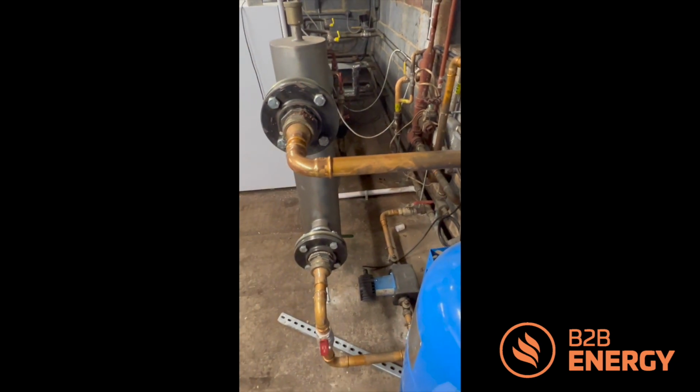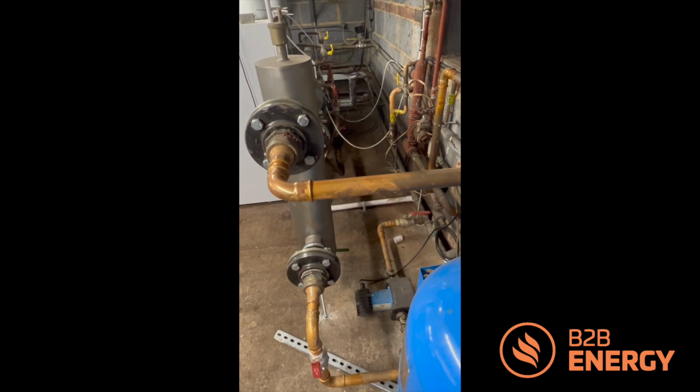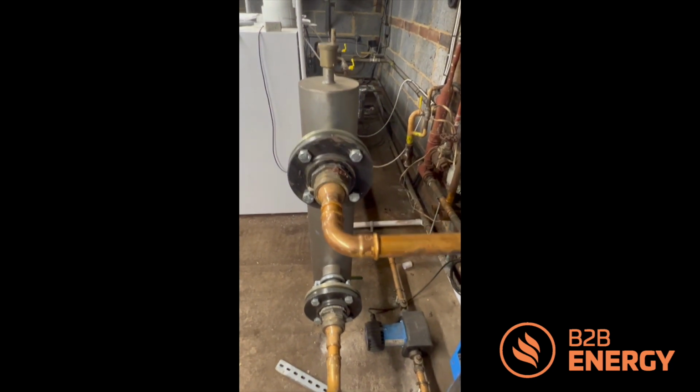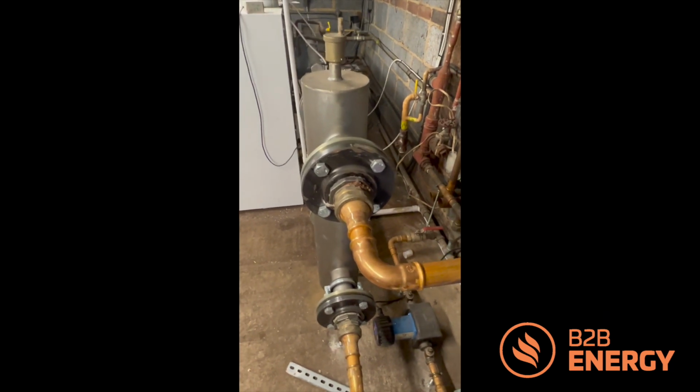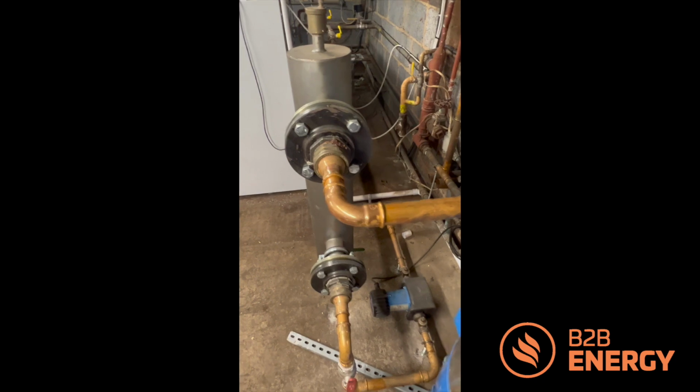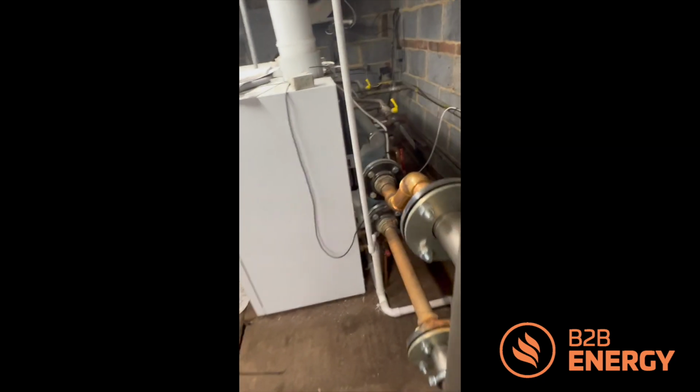You can feel the heat on your face actually at this stage, but if you're not sure whether there's heat coming off, just use the back of your hand to identify any heat there, and in this case there is, and you can see clearly that this is new pipework that needs to be lagged.